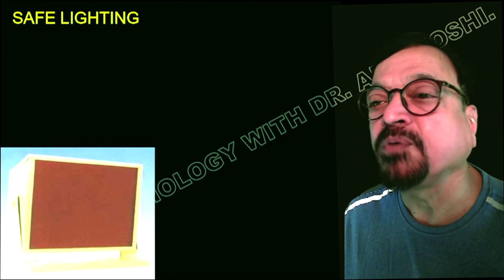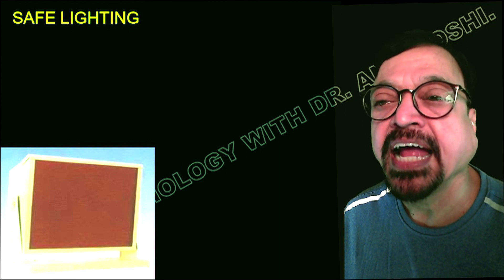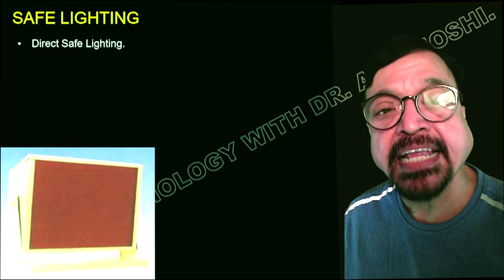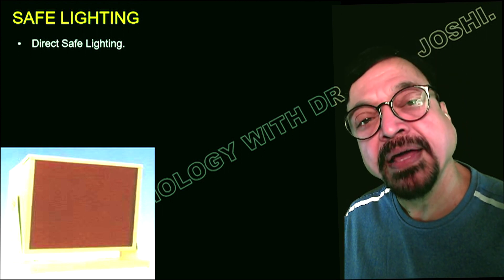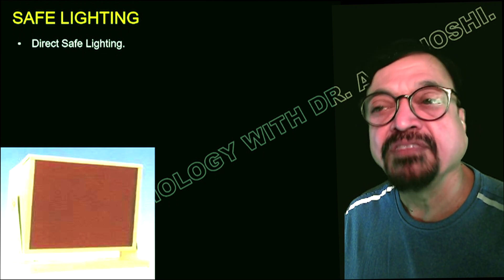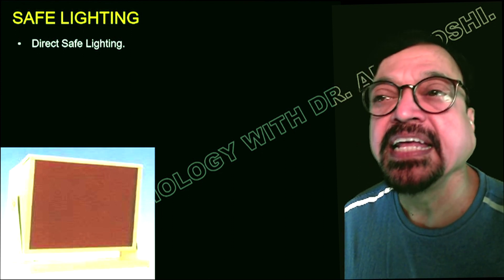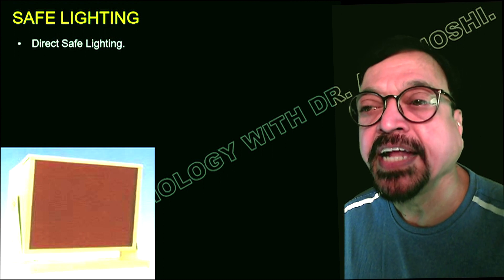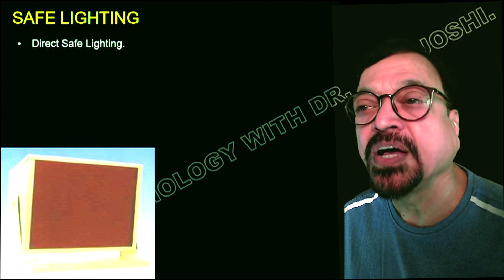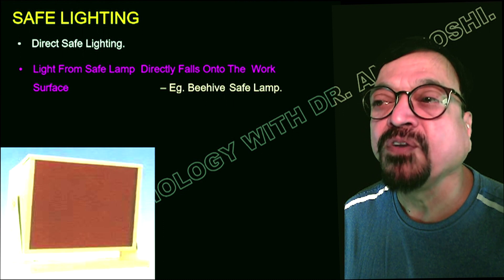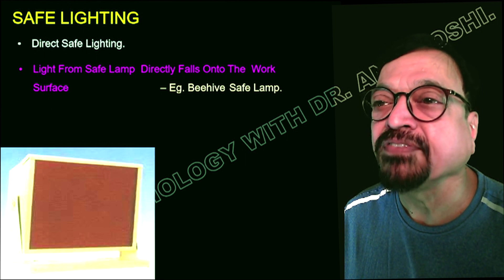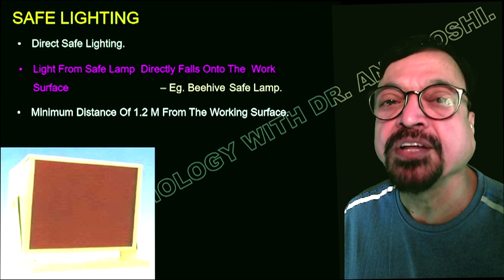Now, this is the safe light. It has got a tin box and there is a filter to it — that is a red filter. So what it does is it gives you only red light out. Why red light? Because films are not sensitive to it. If the film is sensitive and the light has the same color, the film will get fogged. Here, the safe light is of red color because films are not sensitive to red. Films are either blue base or green base — both are not sensitive to red. Light from the safe light directly falls onto the workspace. This type of safe light is called a beehive safe lamp, which gives good light on your workstation.